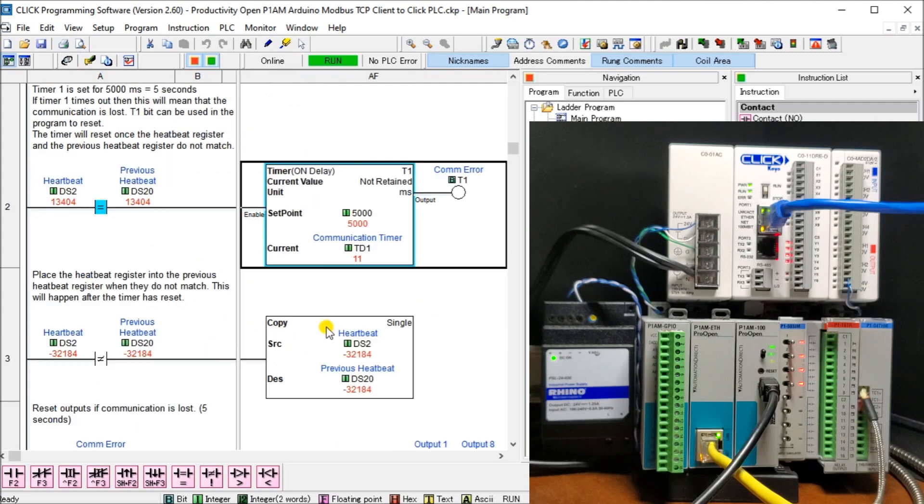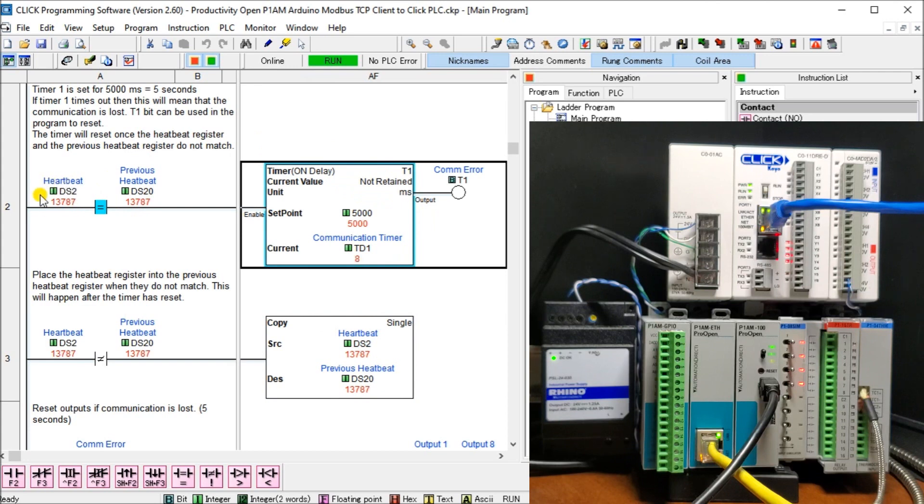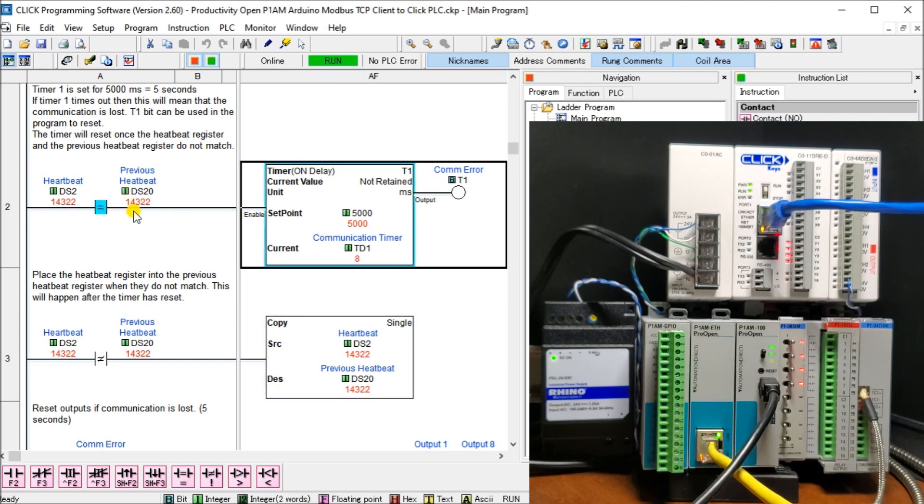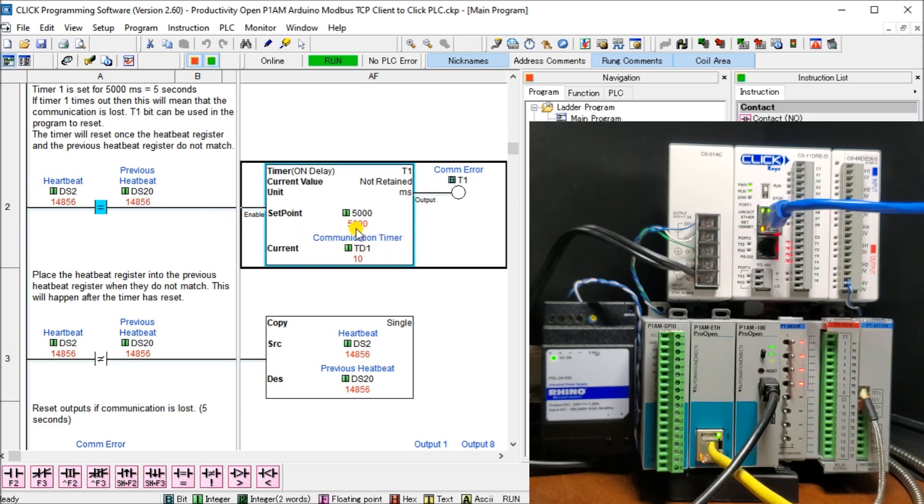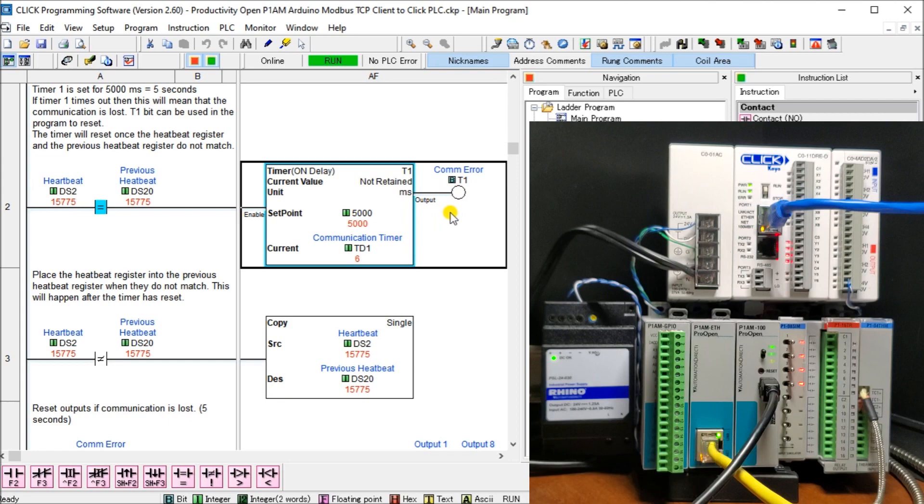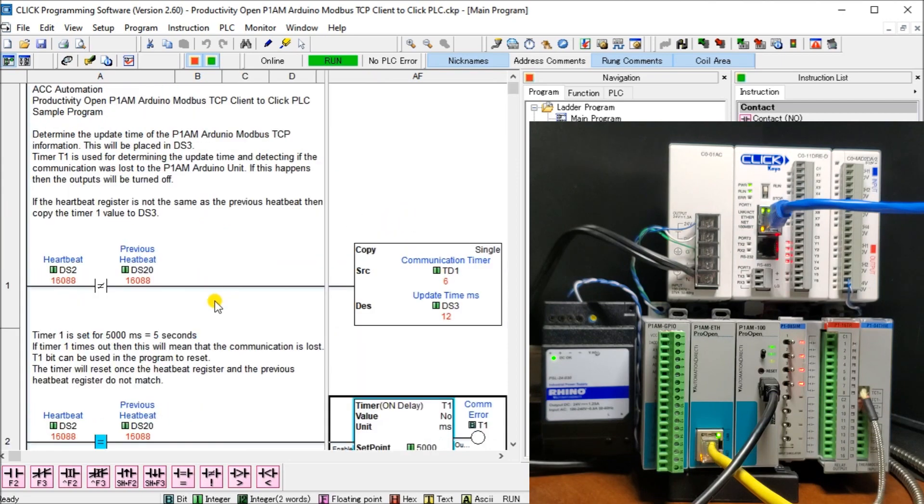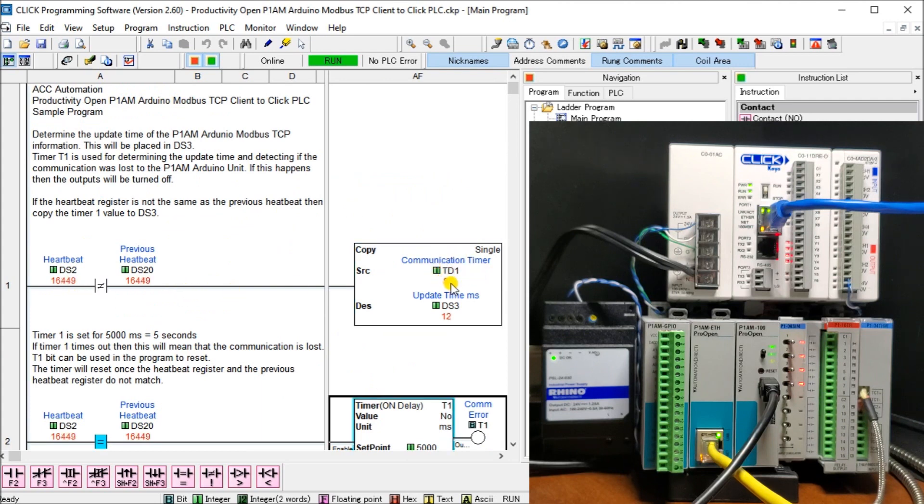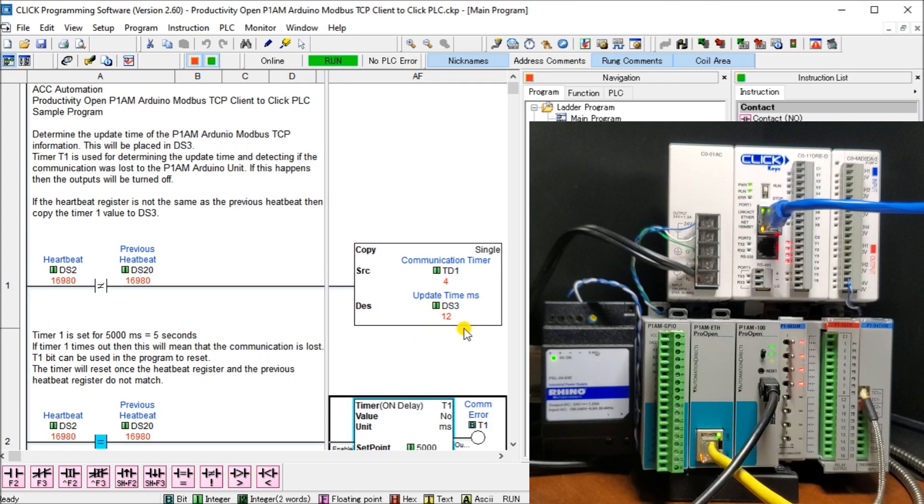So what we do is we set up a timer here. And I have two registers. Here's the register that has the heartbeat, which tells me the incrementing number. And this is the previous heartbeat. And then what we do is if they're equal, then we set a timer and that timer defaults to 5000 milliseconds, which is five seconds. So I've said this timer is actually timer one, which is a comm error. So when that T1 turns on, it means five seconds has passed. And these two numbers are the same. And when these two numbers are not the same, then what we do is we take that communication timer, timer one, and we move it into DS3.